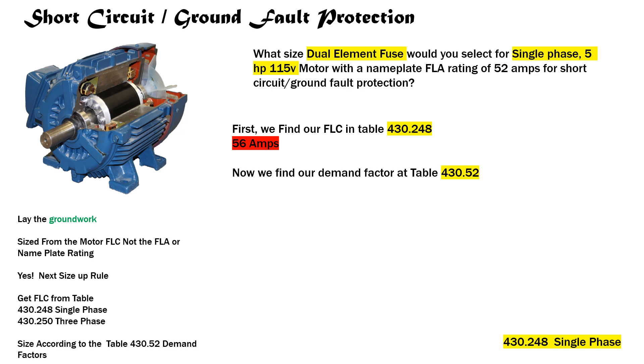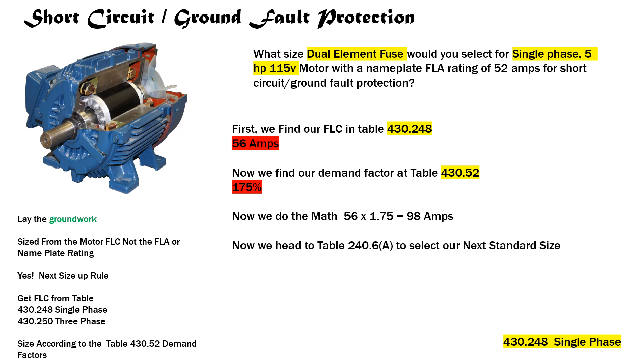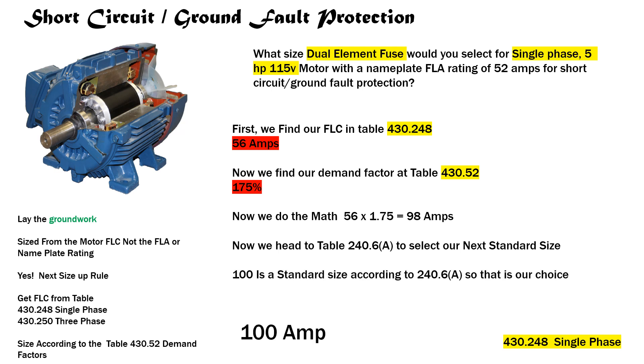We head to table 430.52, start on the left side for single-phase, come across to our type of overcurrent protection, and the demand factor is 175 percent. We do the math: 56 × 1.75 gives us 98 amps. We head to table 240.6(A), select the next standard size, which is 100 amperes. So our short circuit ground fault protection for this motor is 100 amps.